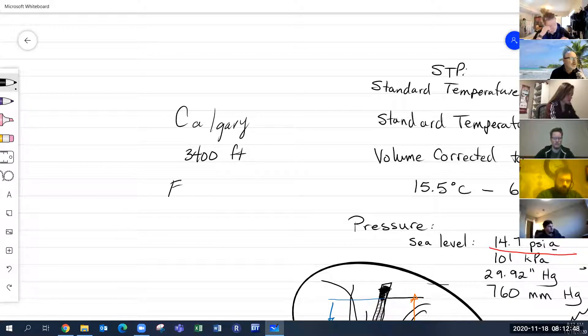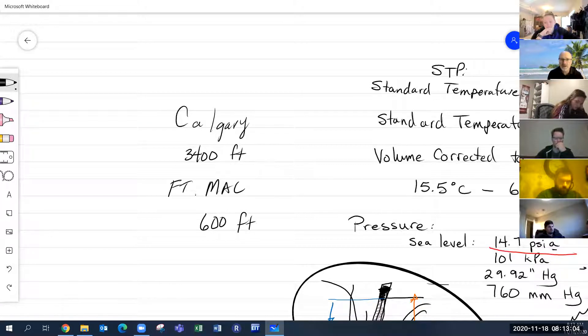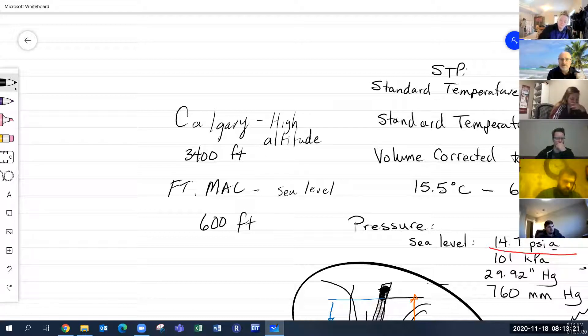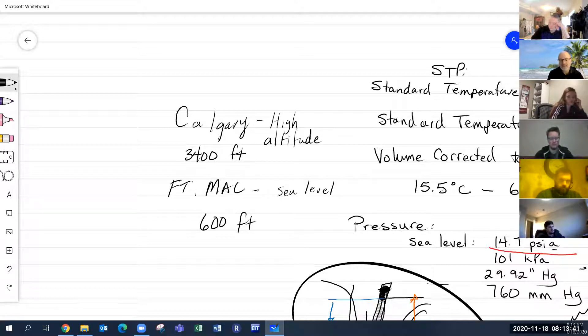Does anybody know the elevation of Fort McMurray? It's about 600 feet above sea level. As we go north, we're actually going lower in elevation. Fort Mac is considered to be at sea level, whereas Calgary is actually considered high altitude. All gas burning appliances in southern Alberta must be rated for high altitude.